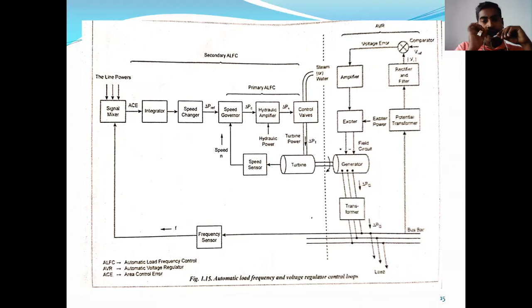The speed of the generator is controlled using the hydraulic amplifier, which leads to the control valve opening and closing. Due to this, the speed is controlled in the turbine, which is connected to the generator. The speed governor and hydraulic amplifier combination is called primary ALFC.